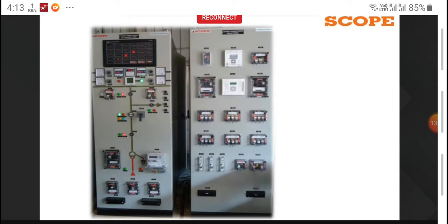And if the operator wants to note the energy parameters, there are the meters you can see here, like the ammeter, energy meters, voltmeter, megawatt meter, frequency meter, all the meters at this control panel. And for any alarm, if we want to see what the different alarms are and where each has come from, he can recognize it from the annunciation panel.